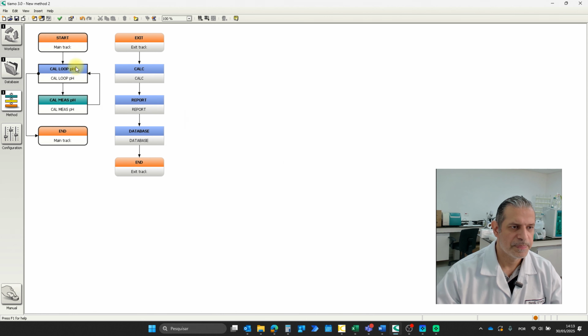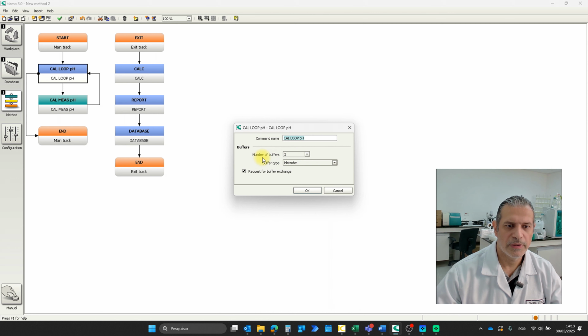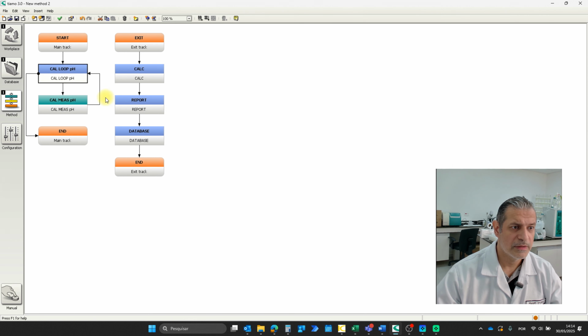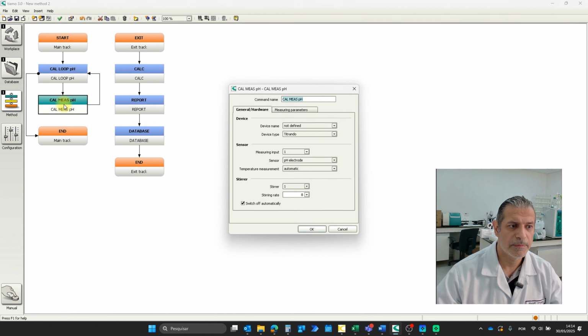Hit OK. Now we are going to change the CAL LOOP pH box. Here we have the number of buffers we are going to use. I am going to use 3 buffers, but it's not Metrohm type. You have a list of different buffer brands that you can use. I'm going to use a special one that is not listed here, and these are the pH buffers I'm going to use: 4, 7, and 9. Hit OK button.